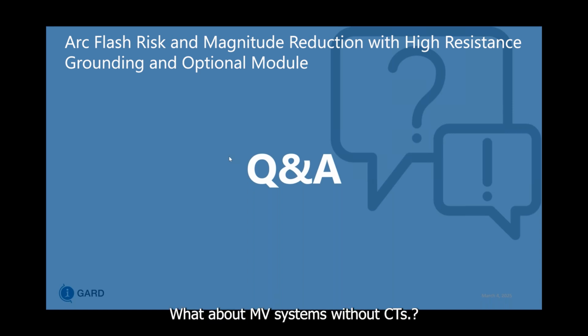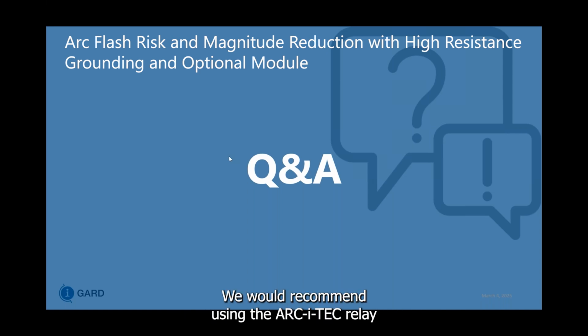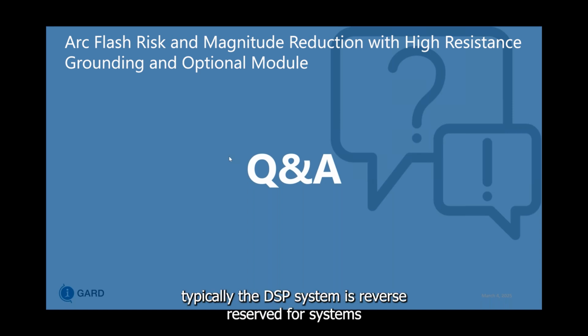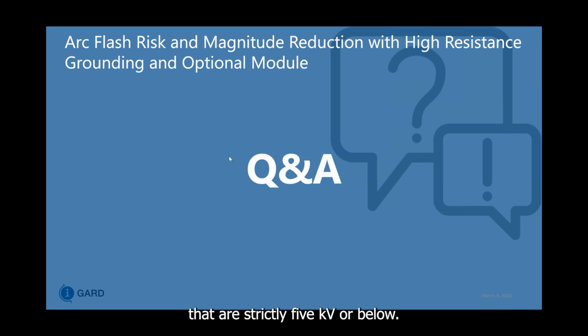What about medium voltage systems without CTs, for example, fuse load break switches? For medium voltage systems, we would recommend using the ARC-i-TEC relay so that you can have CTs and light detection. Typically, the DSP system is reserved for systems that are strictly 5 kV or below.